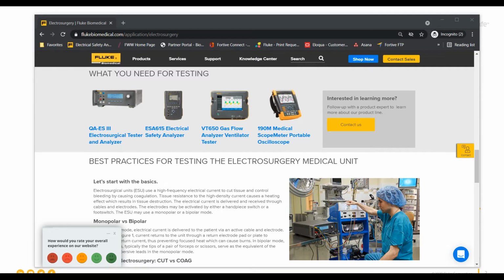How about this? Anybody have an argon beam coagulator? When's the last time you made sure that the argon was flowing at the correct rate? So you might need a gas flow analyzer for this. So the VT650 is a great option for checking out those argon beam coagulators. And way down here on the right, how about this 190M scope meter?